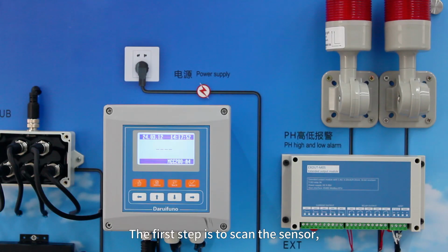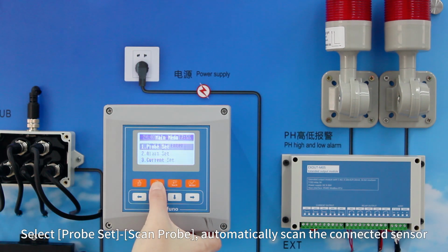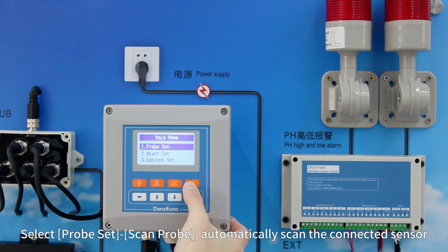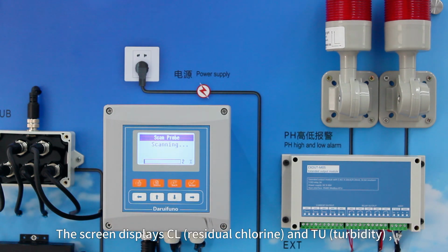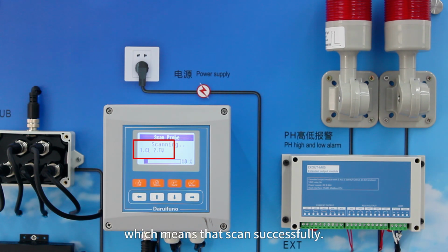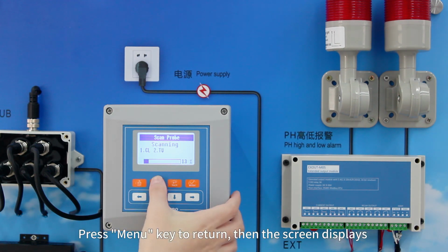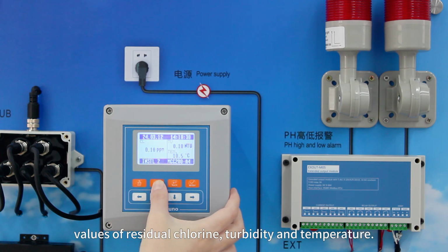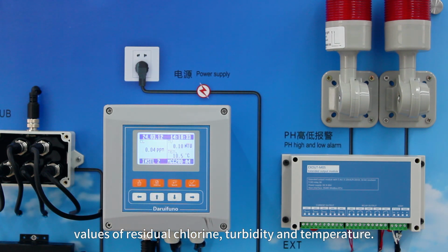The first step is to scan the sensor. Select Probe Set. Scan probe. It automatically scans the connected sensor. The screen displays CL, residual chlorine, and TU, turbidity, which means the scan was successful. Press the menu key to return, then the screen displays values of residual chlorine, turbidity, and temperature.